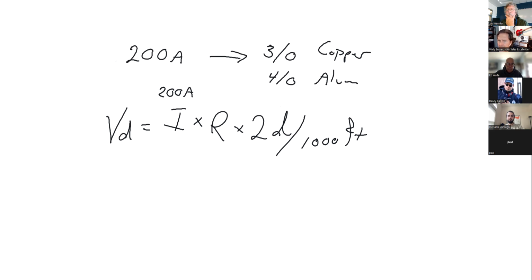It is .0630 ohms. And you said the distance was 650 feet. Correct. So that's 1,300 divided by 1,000 feet.